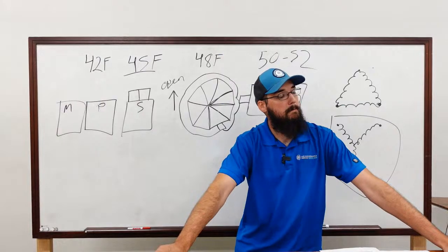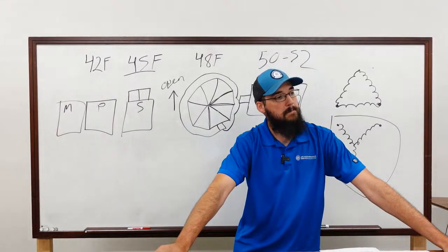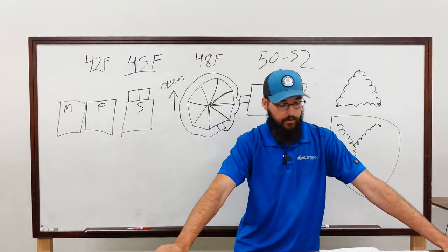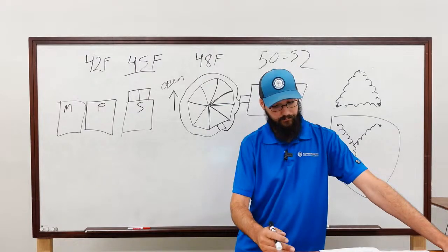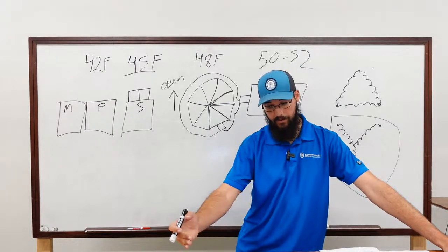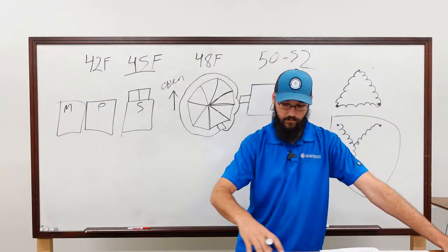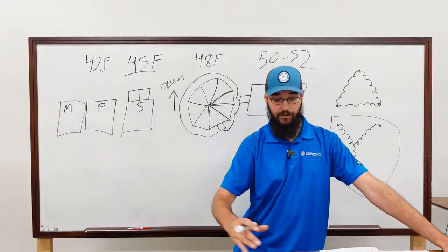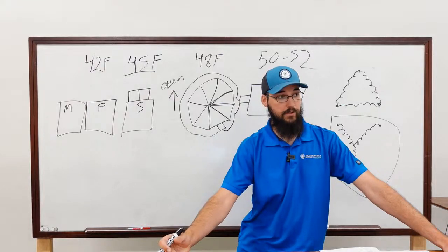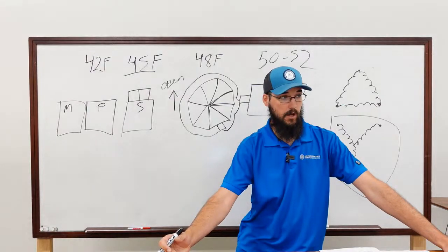The compressors with the drive, how does that respond when you're starting up? You're saying it needs to start unloaded. Does the compressor just, like a soft starter, slowly work its way up? Is it the same principles? Every one of these starting systems, the slide valve or the guide vanes, are going to start at full unload, and they're going to stay there until that compressor reaches operating speed.